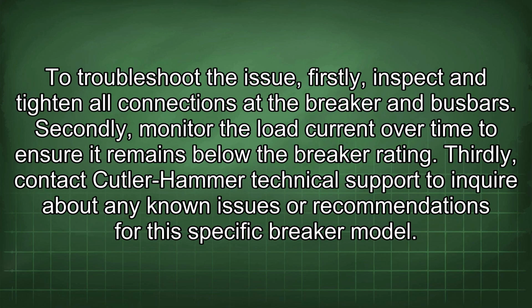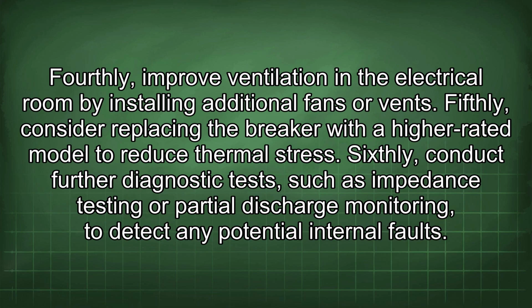To troubleshoot the issue, firstly, inspect and tighten all connections at the breaker and bus bars. Secondly, monitor the load current over time to ensure it remains below the breaker rating. Thirdly, contact Cutler-Hammer technical support to inquire about any known issues or recommendations for this specific breaker model. Fourthly, improve ventilation in the electrical room by installing additional fans or vents. Fifthly, consider replacing the breaker with a higher rated model to reduce thermal stress. Sixthly, conduct further diagnostic tests such as impedance testing or partial discharge monitoring to detect any potential internal faults.